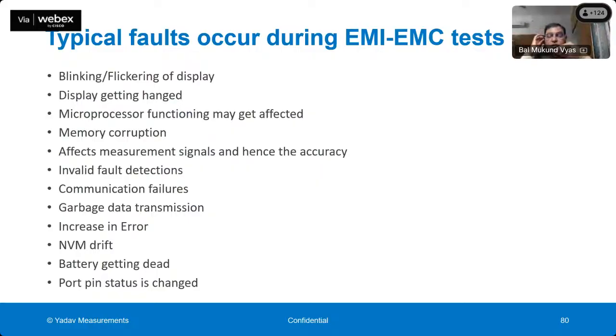Typical faults that occur during EMI-EMC tests, meaning these are various kinds of faults which can happen in the meter. Meter blinking can happen, the display can hang, microprocessor malfunctioning can happen, memory data can get corrupted, and measurement accuracy can be affected. It can detect invalid faults, invalid tampers, communication failures can happen, garbage data transmission can happen, and metrology, memory and battery can get affected, and so on.